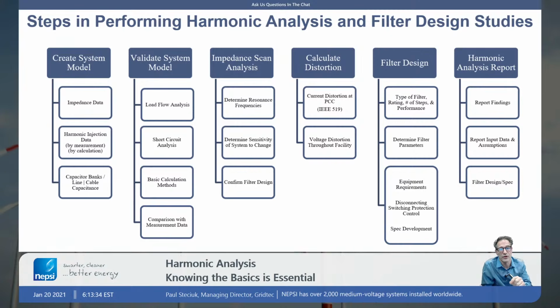We're also looking to determine, well, what is the current distortion throughout the plant? We may have to increase the K factor rating, for instance, of a transformer if we have a lot of harmonic current flow. Also, we're looking to calculate current flow also. Filter design is an output of a study. We got a problem. We need to improve the power quality within the plant. We need to do some type of filtering. We need to be compliant with the harmonic standard for the interconnecting utility. So we develop a filter and we verify that filter design.